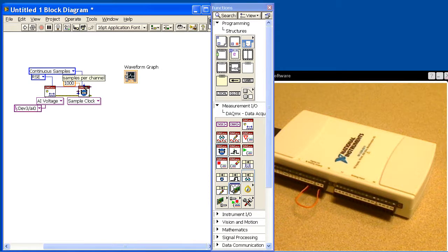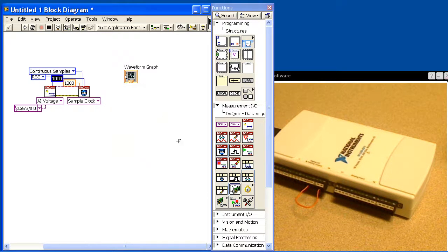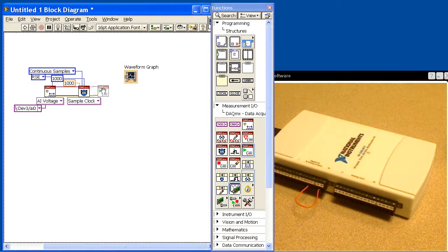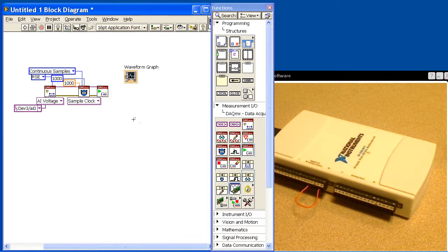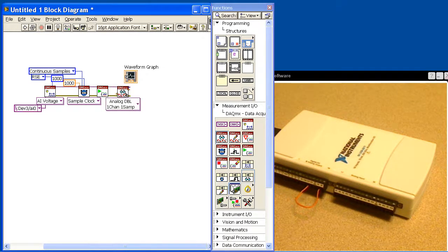The next thing we need to set is the number of samples per channel. We'll create a constant and leave it at one thousand. It uses this number to size the buffer in memory that the 6211 will stream data into. After that we simply need to start the acquisition, and then we're going to be reading out of that buffer that we allocated in our previous VI.